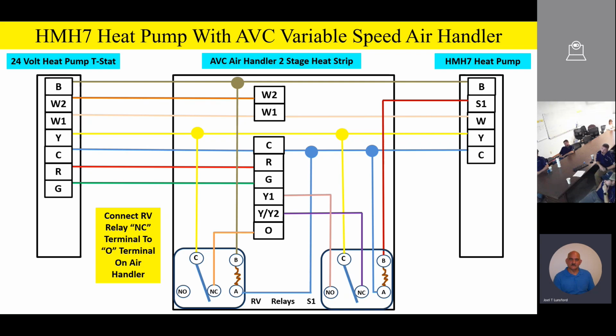In the heating mode of operation, we want to tell the air handler that we no longer have the O signal in the heating mode. And so that's exactly what that relay is for. The only reason that relay is there is to switch the O terminal off in the heating mode. But in the cooling mode, we want to have power going to the O terminal on the variable speed indoor product for some advanced dehumidification and some advanced fan functions.